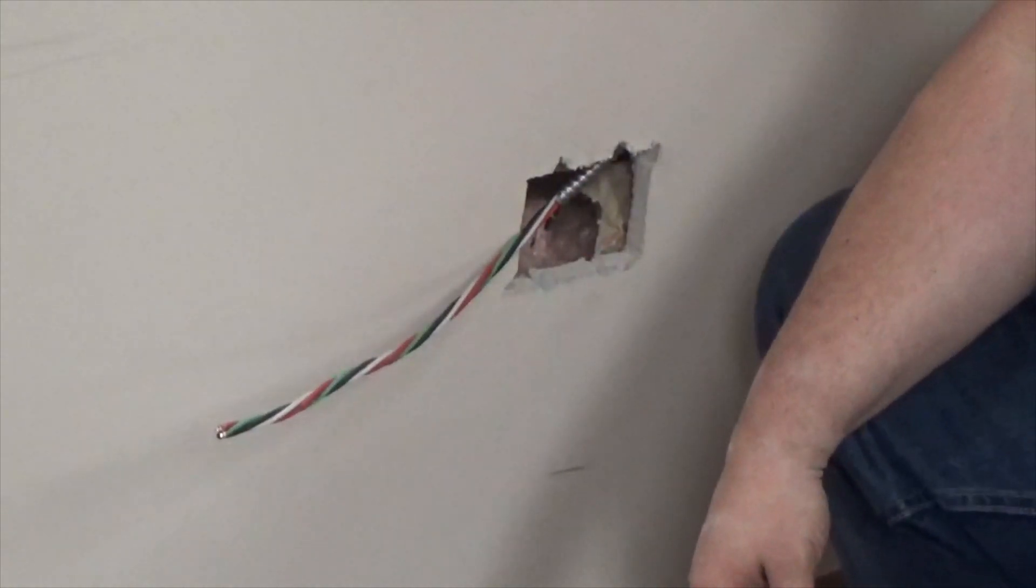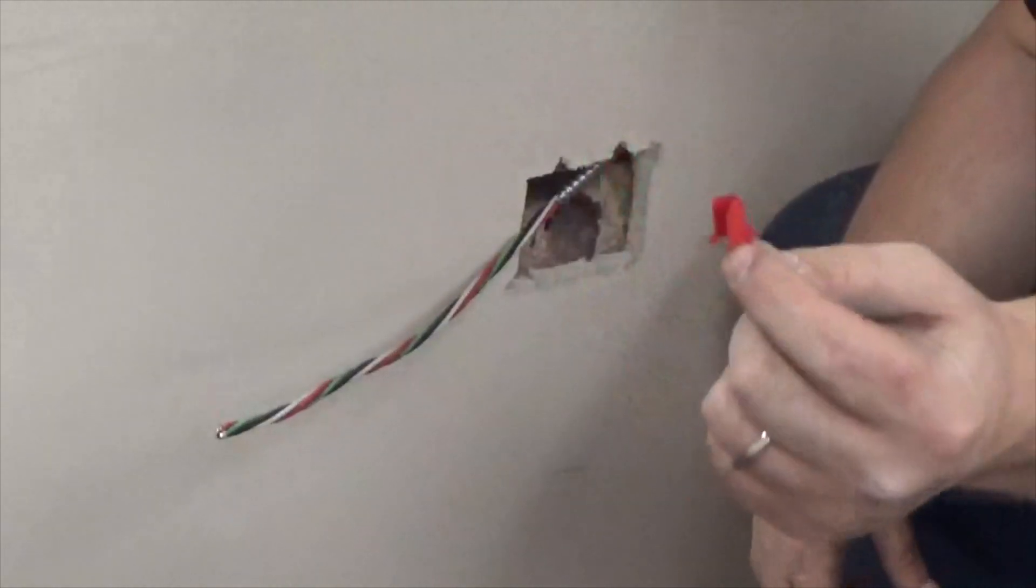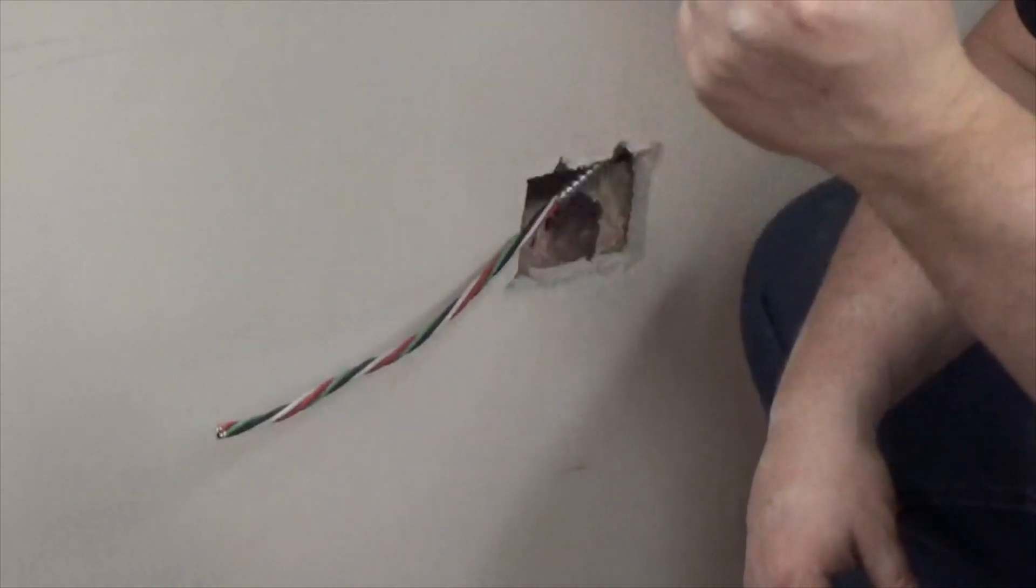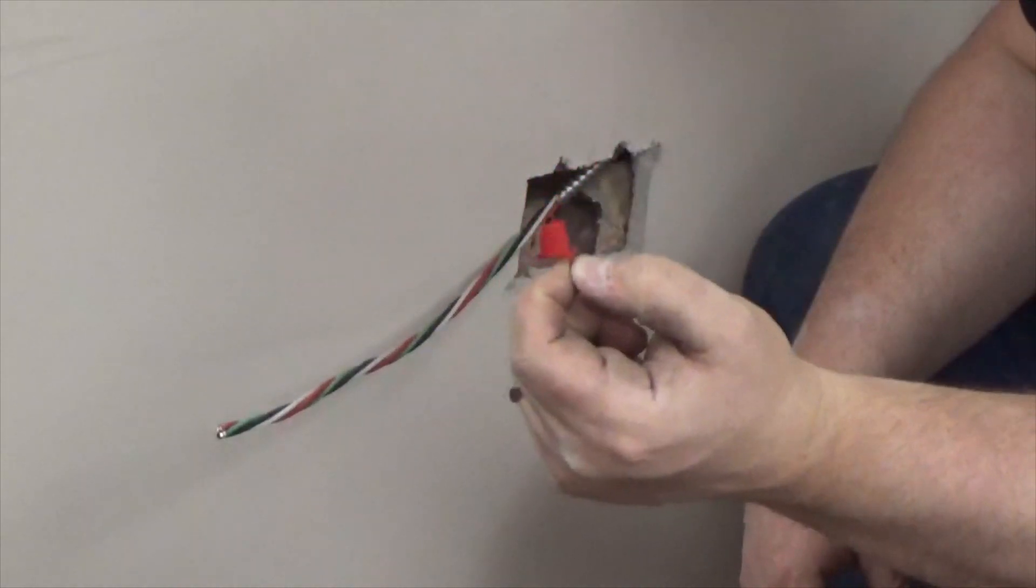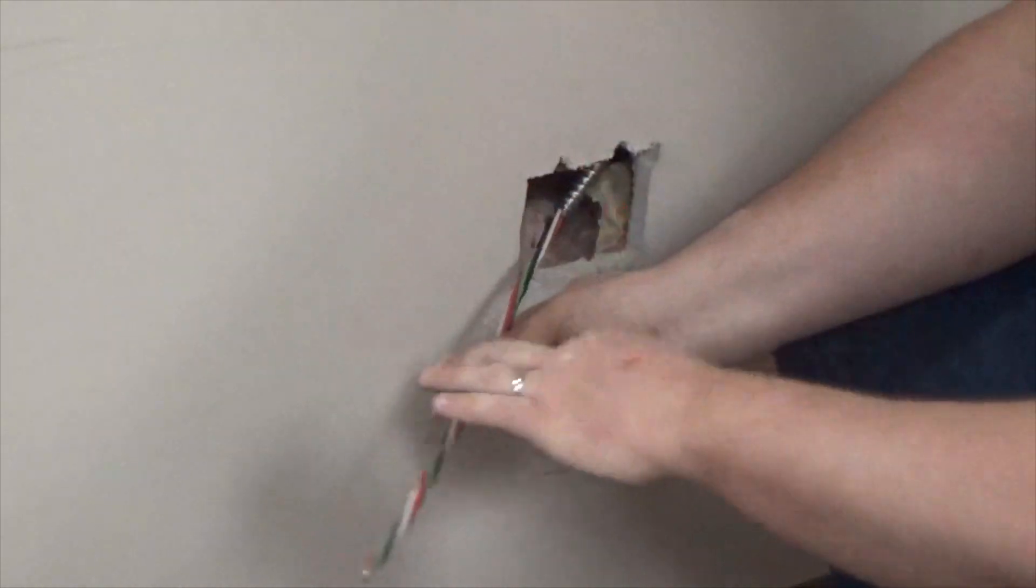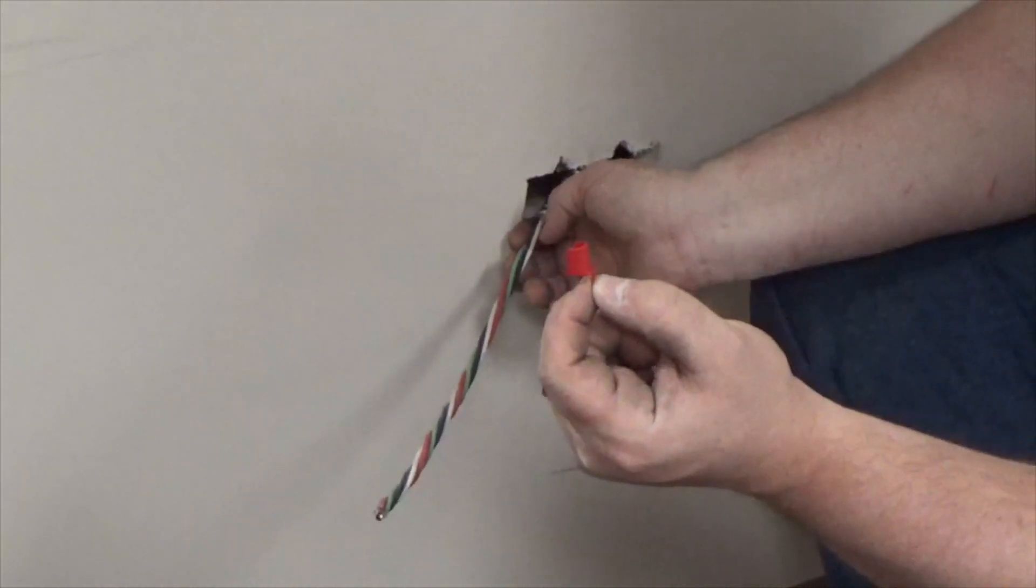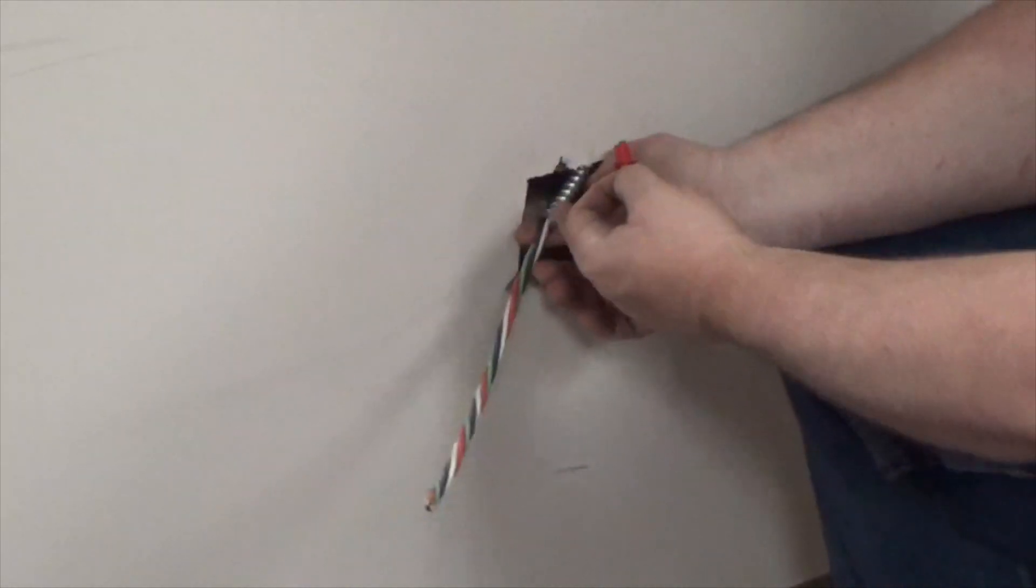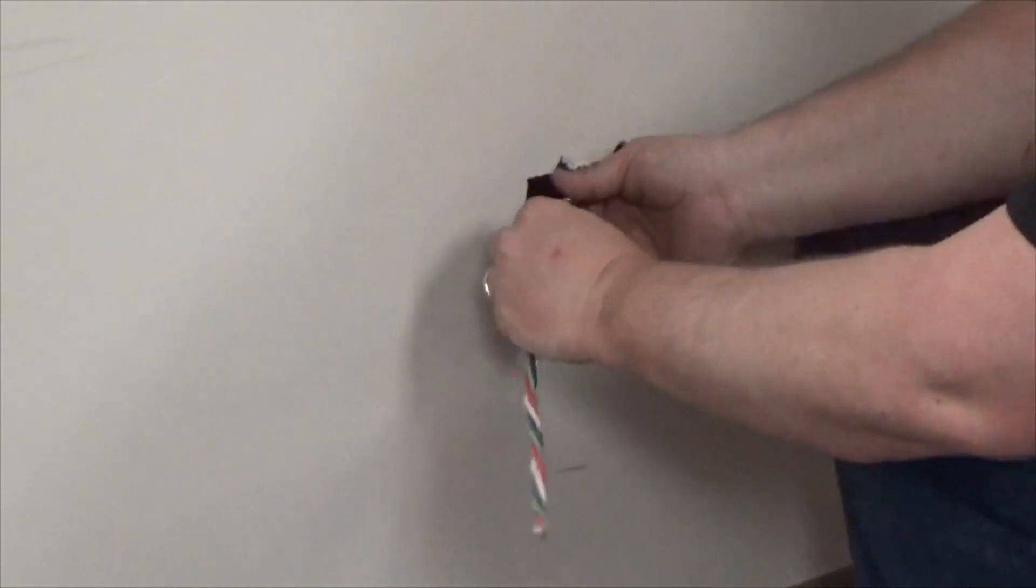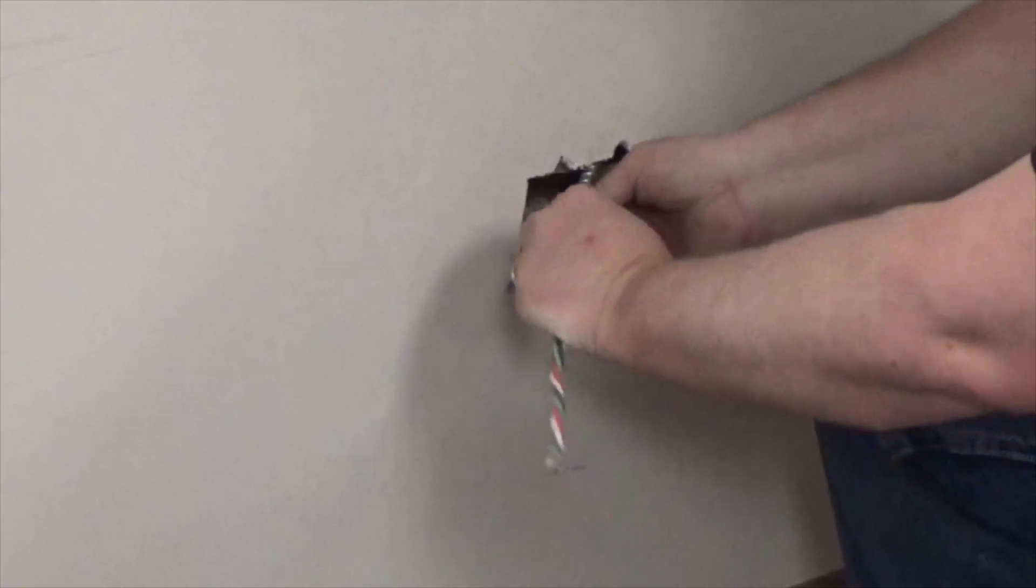So, one of the things in 2011, these here called a red head or a red devil or an anti-short bushing. These were not necessarily required in the 2011 code. I always tell my guys, if you work for me, you're going to use red heads because I just feel more comfortable with them there because this metal edge touching my conductor is bad. So, are they required? They are not required, but they are required if you work for me.